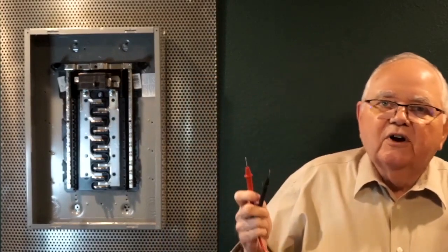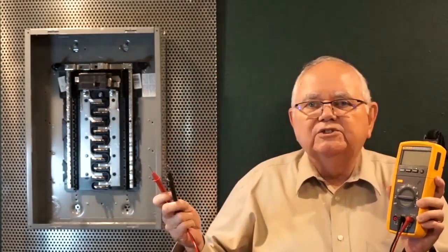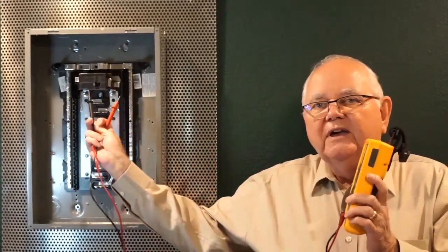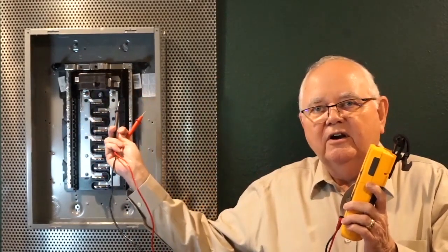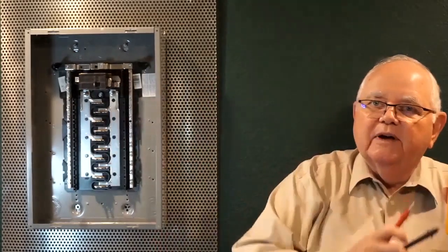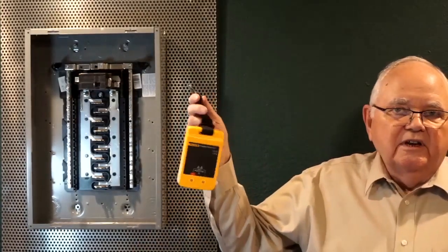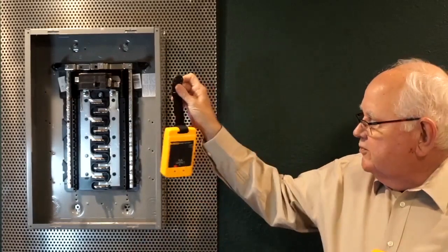We first make sure our meter works properly on voltage. Then we check from phase to phase and phase to ground on our equipment. And then we go back and make sure that the meter still works properly on voltage. Now I could use a receptacle in order to make sure that my meter works properly. One of the most common things that we see a lot of out in the field is various types of proving units.